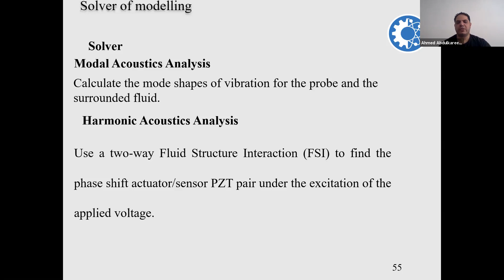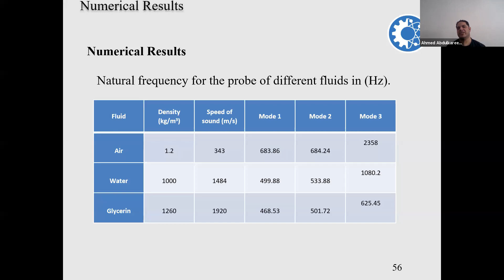Right here, the numerical result shows the natural frequencies for the probe. When I say natural frequency, I mean I don't have any load. I just model the probe immersed in the fluid. So right here we have the natural frequency for the probe in different fluids, in hertz. We have the air, the water, and the glycerine. Usually all these are correlated to the density and speed of sound. I have mode 1, mode 2, and mode 3.